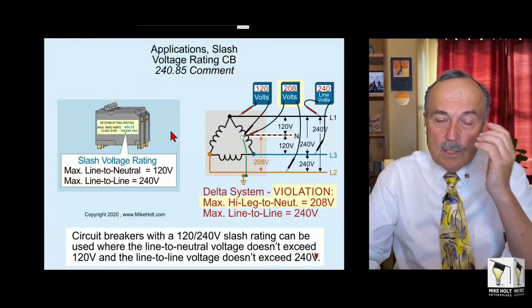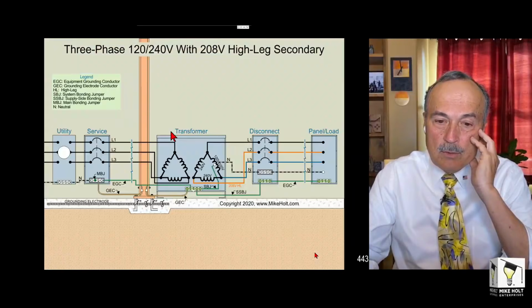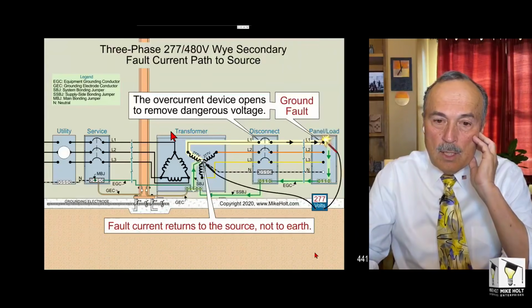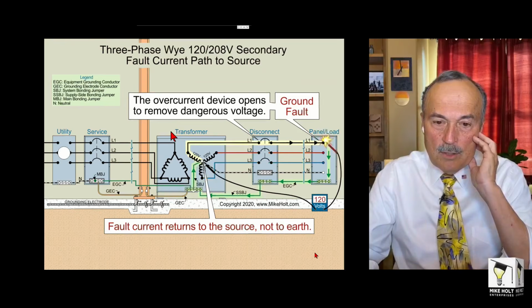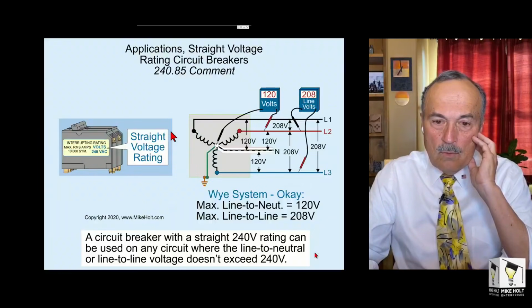Okay. We got another one. If the system does not have a system bonding jumper, will the disconnect still work? And what would happen if the ground fault would occur before the secondary disconnect on the secondary? I don't know what system we're talking about, so let me go over to something that people can relate to a little easier. So let's go over to a three-phase 120/208 volt system.